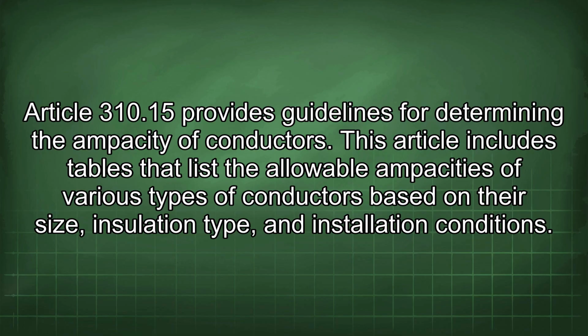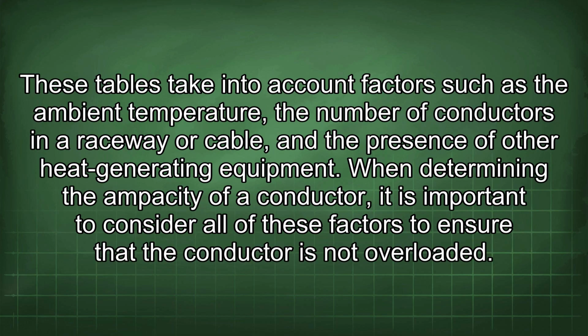Article 310.15 provides guidelines for determining the ampacity of conductors. This article includes tables that list the allowable ampacities of various types of conductors based on their size, insulation type, and installation conditions. These tables take into account factors such as the ambient temperature, the number of conductors in a raceway or cable, and the presence of other heat-generating equipment. When determining the ampacity of a conductor, it is important to consider all of these factors to ensure that the conductor is not overloaded.